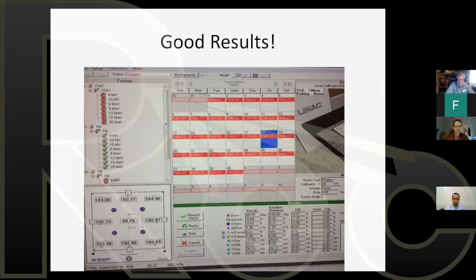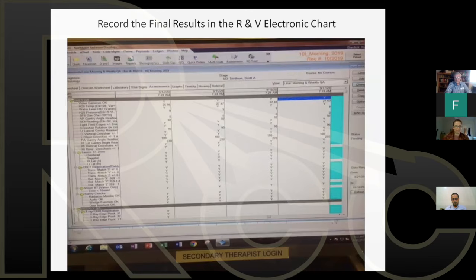So we were here where I said good results, but also if you're using a record and verify system, Elekta has a record and verify system. This is the one that I'm familiar with. It's Mosaiq. Now, the Mosaiq system allows you to program into an assessment sheet LINAC morning and weekly QA. Look at this. So the physicist has programmed into an assessment in Mosaiq all of the things that the therapist checks on a daily basis.